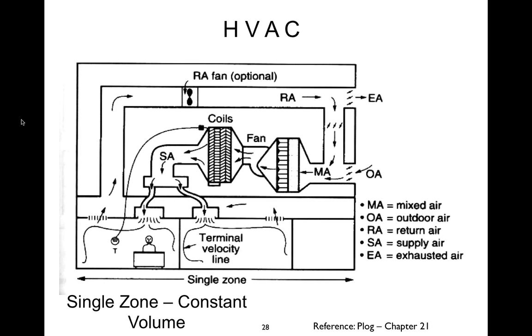What they did about that was they designed minimums into those things. So even though you're not getting what the architect would like you to get every minute, your 6 air changes per hour, they stay open enough and compromise the temperature enough that maybe you get 2 or 3 air changes per hour. So you still get some air movement, even if the temperature is satisfied, right? So those are called variable air volume systems. We got one here. That's a thermostat that's on the wall. It wouldn't be here if we didn't have a variable air volume system.